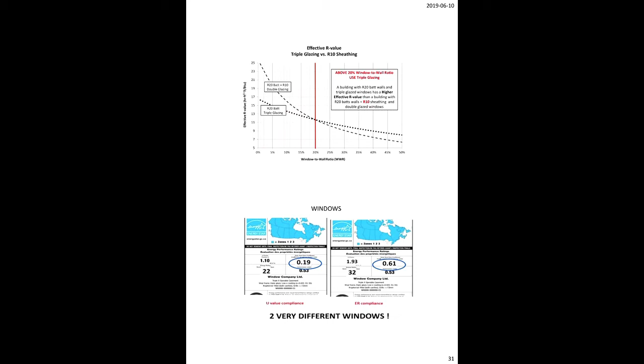Keep them together. The other thing to keep in mind is when you do your calculations for your heat loss and heat gain, the solar heat gain number will contribute almost up to 50% of your total air conditioning or cooling load on the house. Air conditioning loads are the fastest growing peak load that we have right now. We've got more windows. The geometry of the house is changing. We're finding that it's actually causing our ductwork to get bigger.